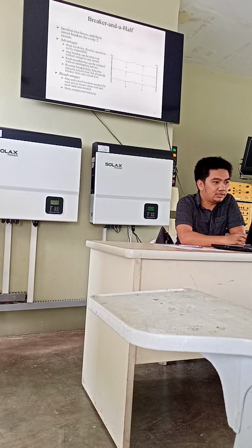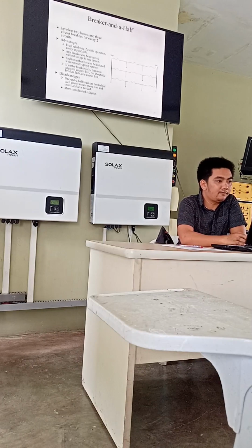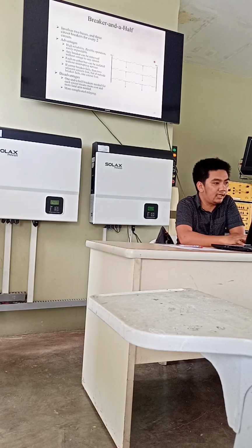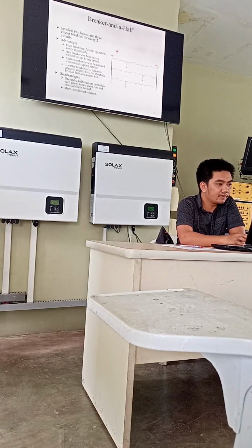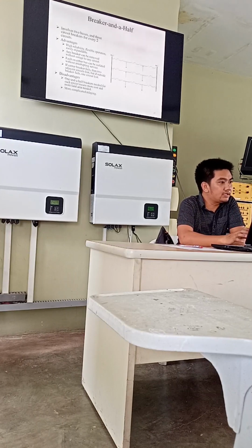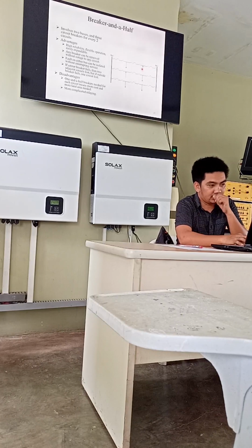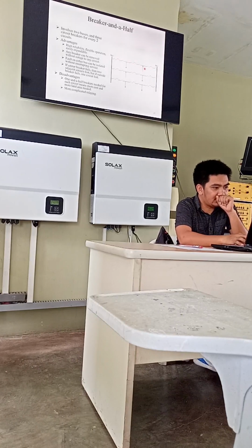Why is it that this one is a good design for a distribution substation? It provides high reliability and flexible operation, and it can easily be expanded. Any breaker can be removed without the outage of any circuit, and faults on either bus can be isolated. But if the center breaker fails, then the two adjacent circuits are lost. If an outside breaker fails, only one circuit is lost. But there are disadvantages.